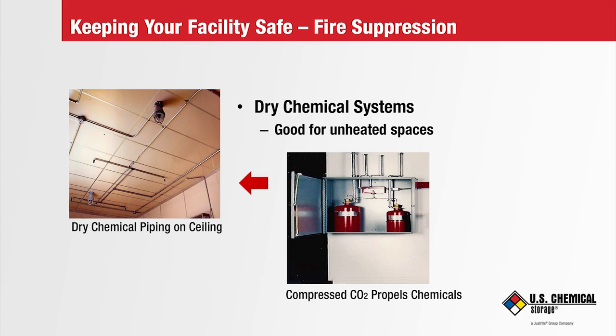On the cable, fusible links are distributed at predetermined distances, so that when the temperature from a fire reaches the melting point of any single fusible link, the cable is cut. This will release the valve of the compressed CO2, pushing the dry chemical powder into the piping and out of all dispensing heads at the same time.